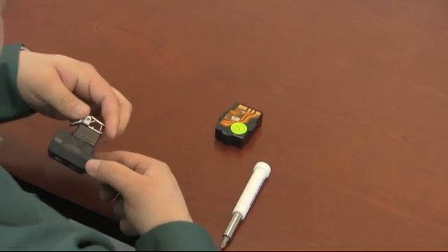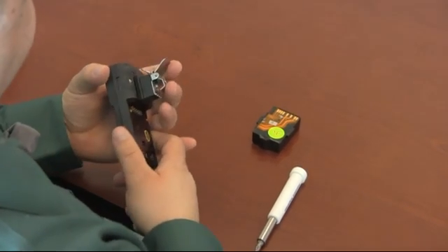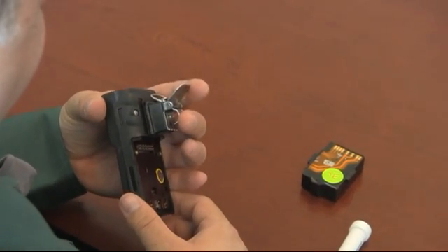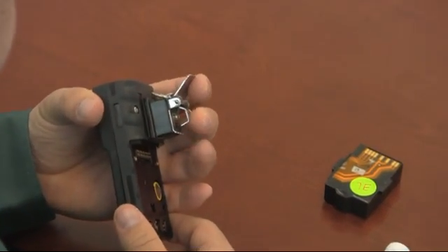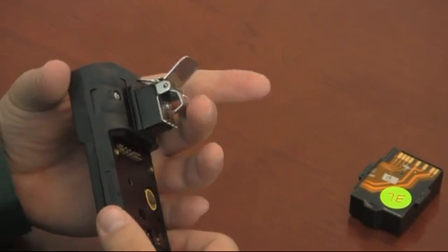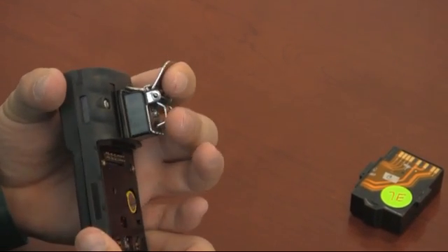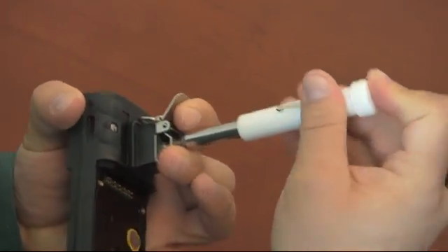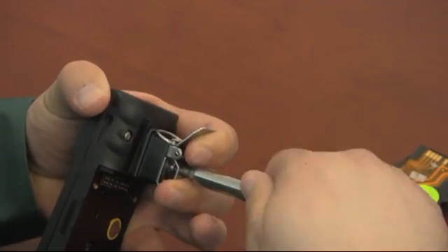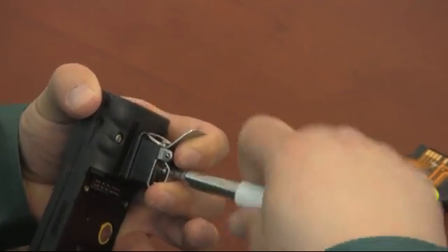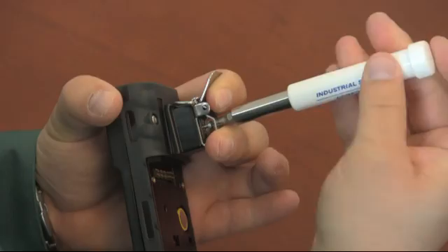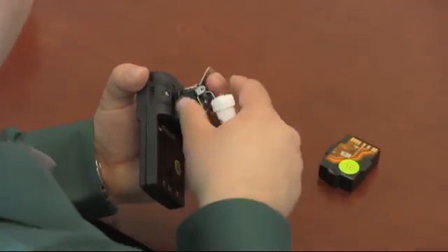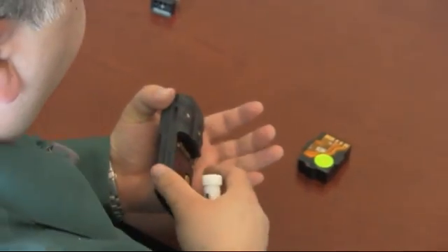Next we'll take off the suspender clip and the spacer. This can more easily be done with a smaller screwdriver, but I want to demonstrate how I typically do it using the included maintenance tool with the instrument. I push back on this tab and push down on the clip, and it gives you a little more access for the screwdriver head. Put those aside.